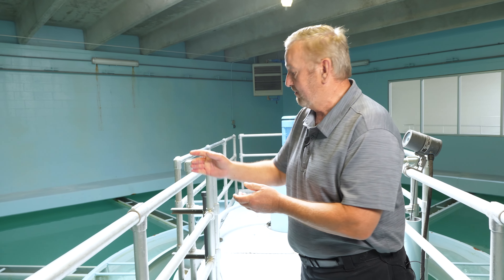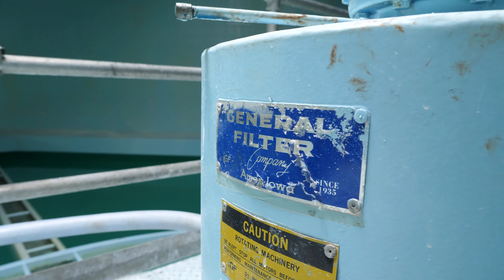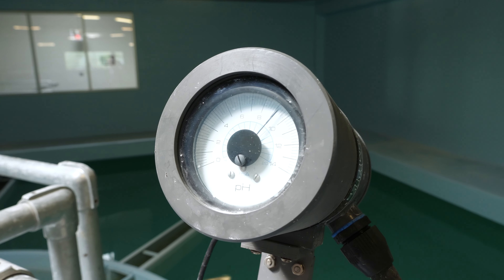If you look behind you, the lime is added to a center area — it takes hardness out of the water and drops to the bottom. Softened water rises, is collected in the weirs, and sent to the next part of the process: filtration.